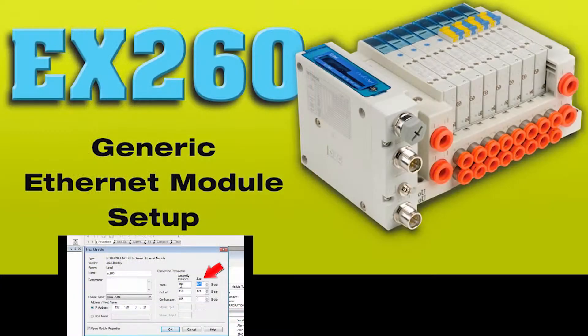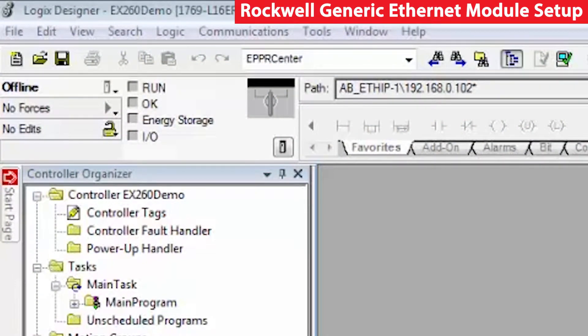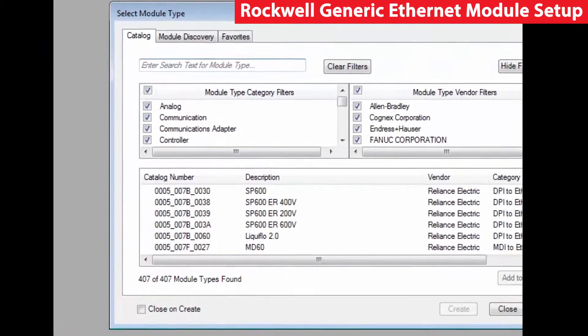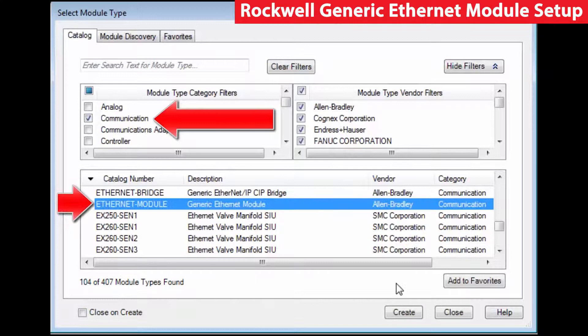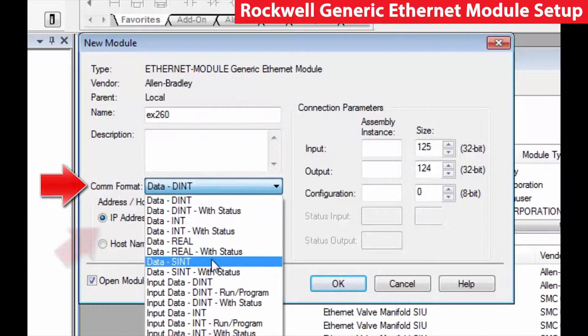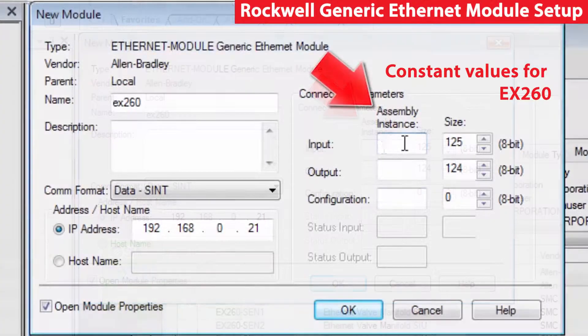You can also set up the EX-260 with a generic Ethernet module. To do so, connect the Ethernet cable to the EX-260 and start a session of RSLogix 5000. No EDS download is needed this time, but this method takes more effort. Select the master in the controller organizer and select New Module. In the Select Module Type table, select Generic Ethernet Module and click Create. In the New Module Type, enter the desired unit name first, then enter the comm format type, and then the IP address that was set for the unit.